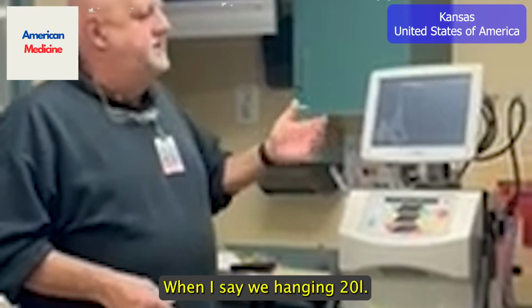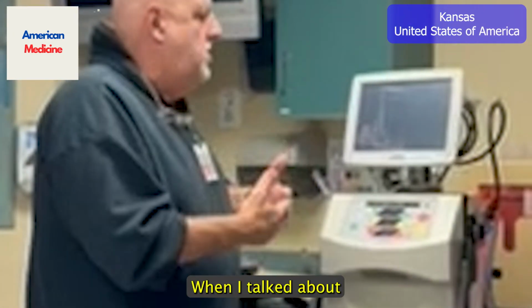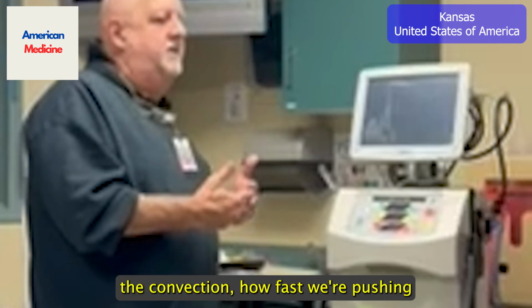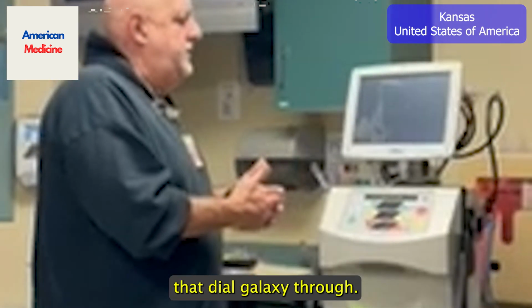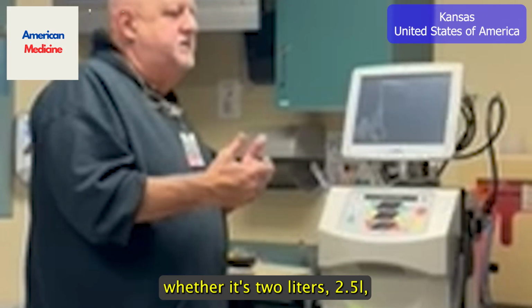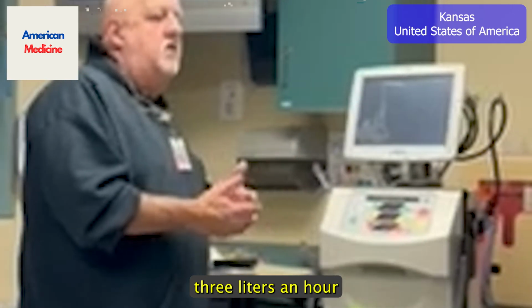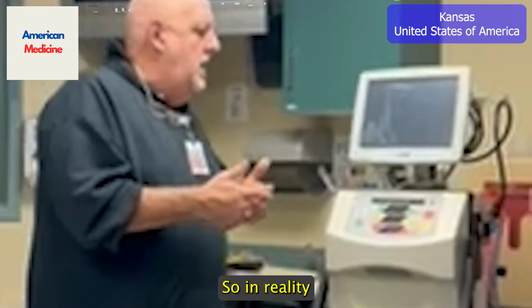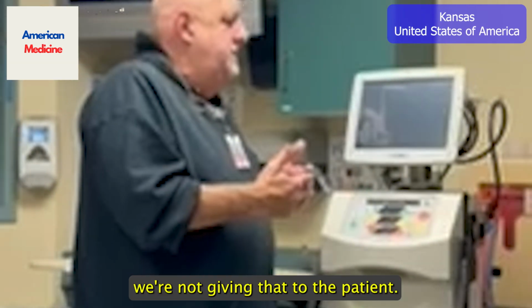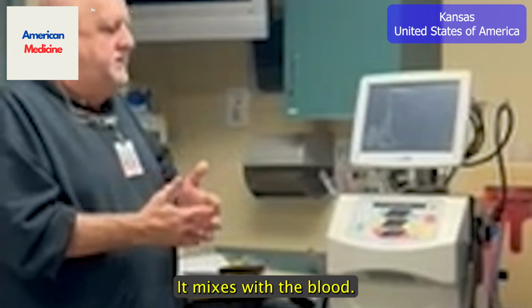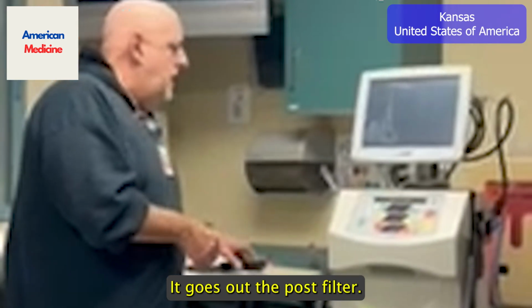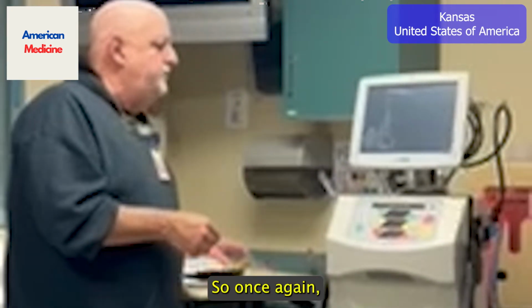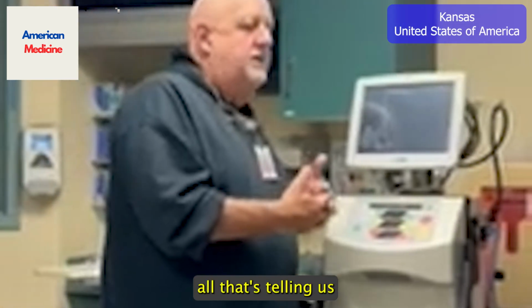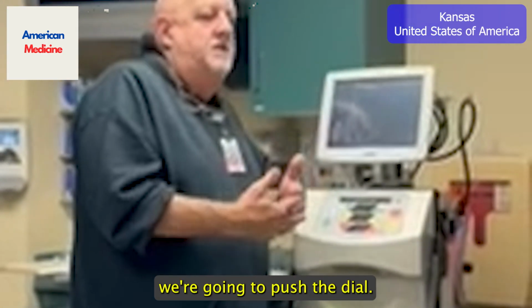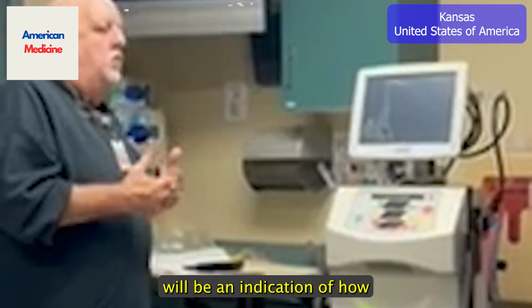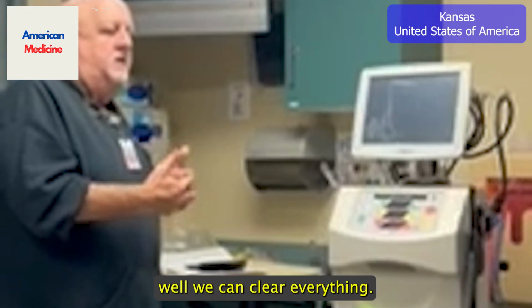Now, when I say we're hanging 20 liters, when I talked about the modality of the CRRT, the convection, how fast we're pushing that dialysate through, just remember, whether it's 2 liters, 2.5 liters, 3 liters an hour, that will never get to the patient. So in reality, we're not giving that to the patient. Basically, it goes in pre-filter, it mixes with the blood, it goes out post-filter. That will go to a drainage system. So once again, all that's telling us is how fast we're going to push the dialysate through the machine will be an indication of how well we can clear everything.